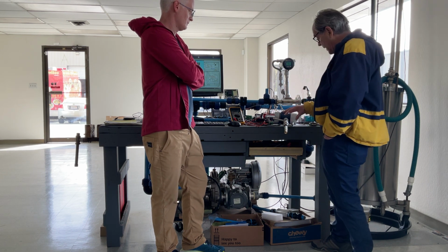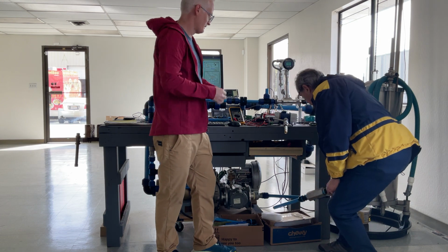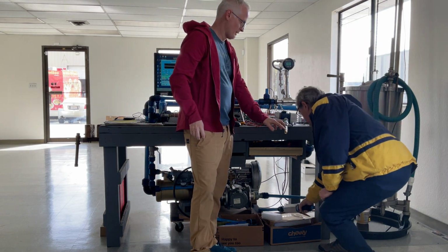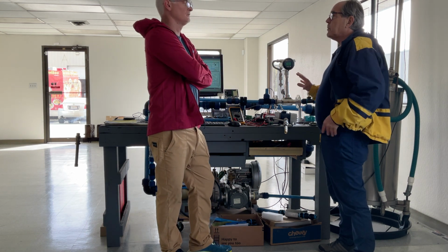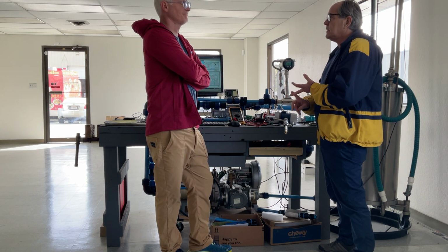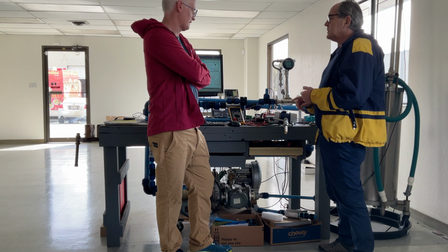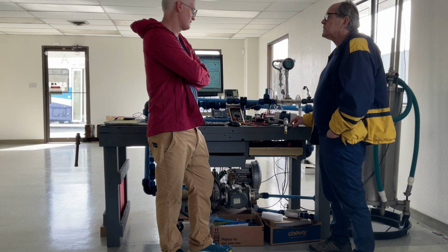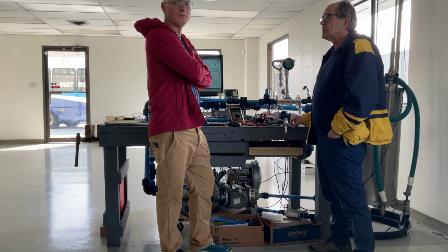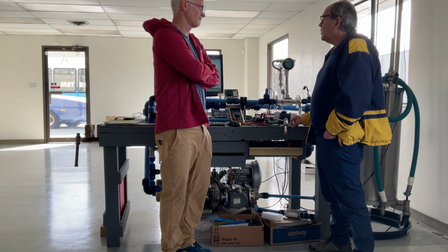In another meter we have this meter. Hold on, let's back up on that one, because different gases have different heat conductivity. They have all the different properties: density, viscosity, thermal conductivity. So you have to calibrate it based on your material. And I guess the material is usually what they say it is, but maybe not all the time? No, it isn't always.